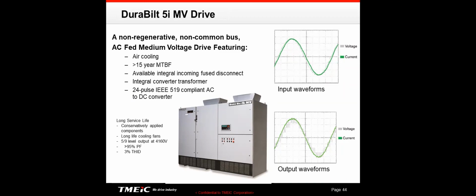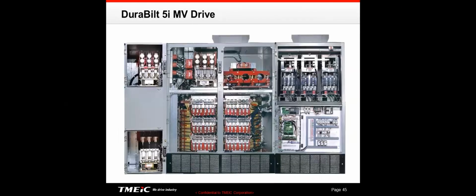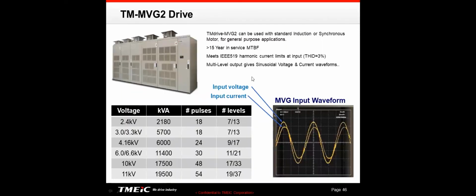24 pulse drive is going to get you well below 5% in terms of your harmonics and give you a very, very good waveform that you can see there. So this particular drive has a 24 pulse input and a 5-level output, which is pretty good. And there is a picture of that. Again, there's the isolation transformer, and then you have your converters and your inverters downstream.